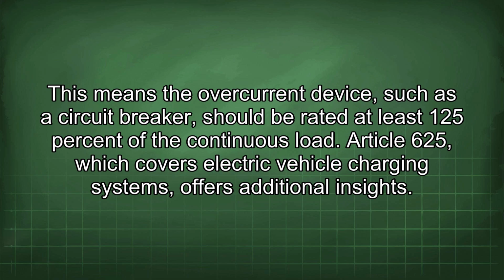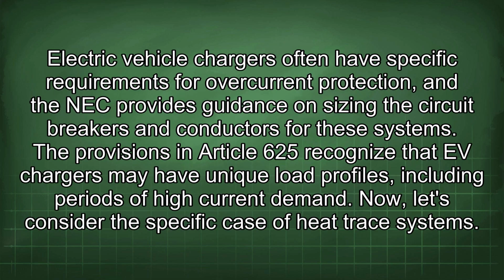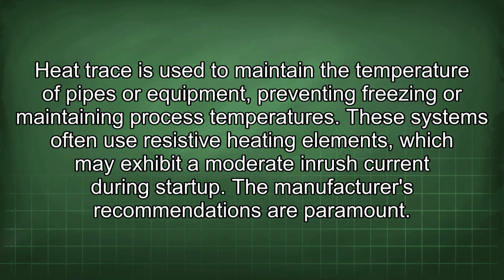Article 625, which covers electric vehicle charging systems, offers additional insights. Electric vehicle chargers often have specific requirements for overcurrent protection, and the NEC provides guidance on sizing the circuit breakers and conductors for these systems. The provisions in Article 625 recognize that EV chargers may have unique load profiles, including periods of high current demand. Now let's consider the specific case of heat trace systems. Heat trace is used to maintain the temperature of pipes or equipment, preventing freezing or maintaining process temperatures. These systems often use resistive heating elements, which may exhibit a moderate inrush current during startup.